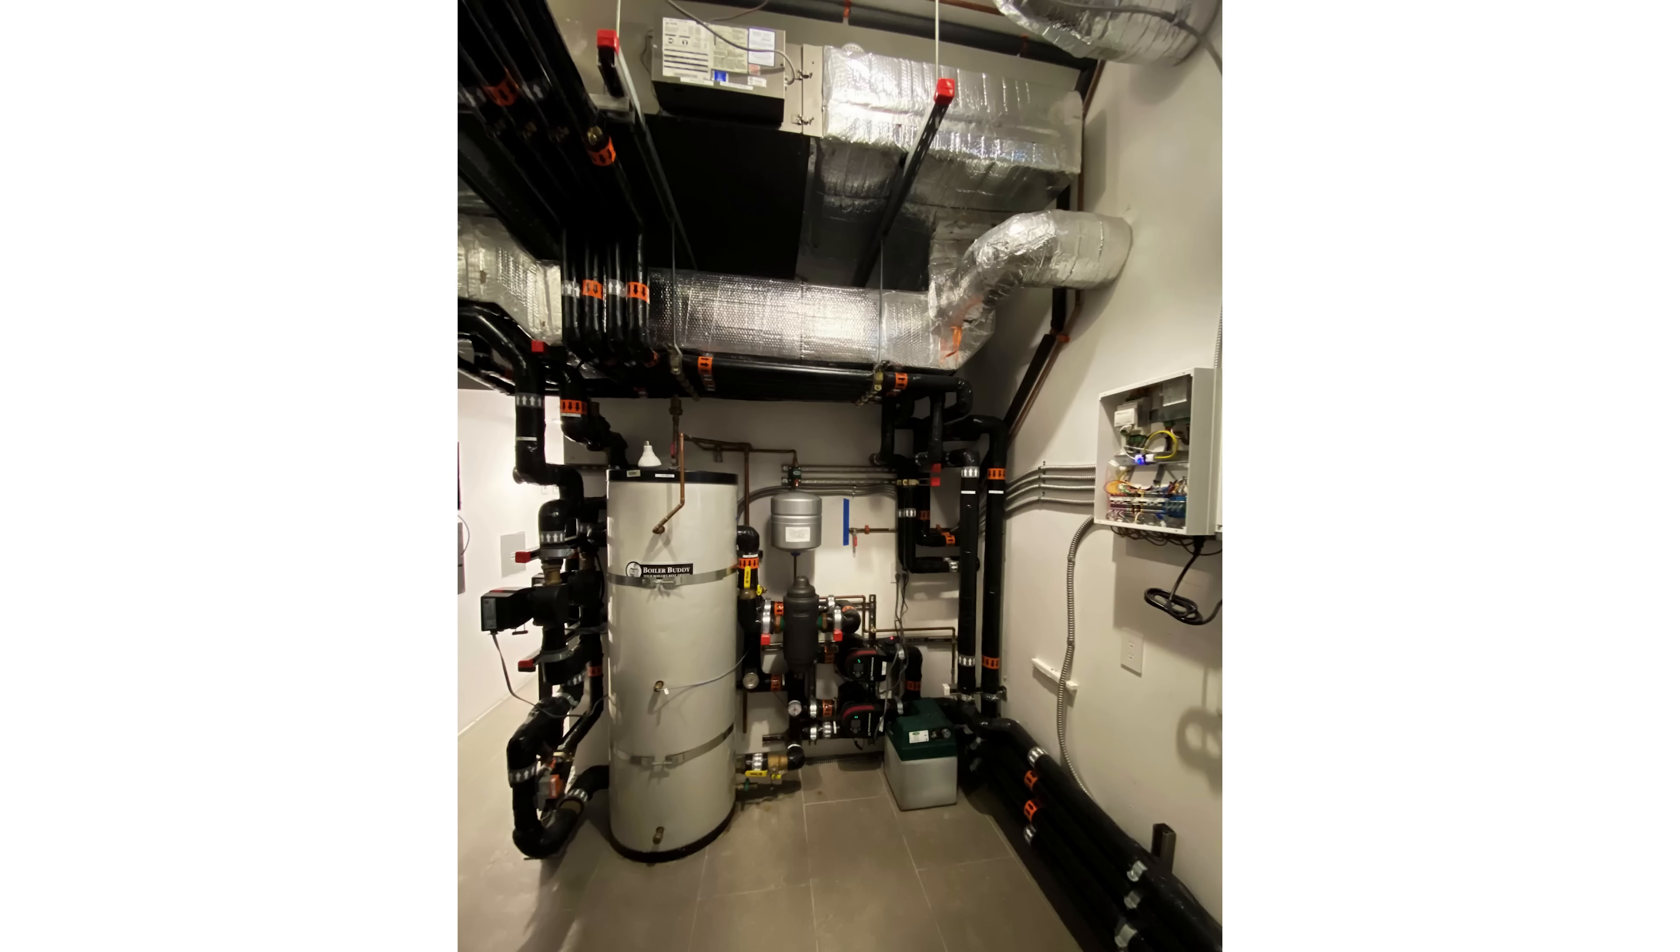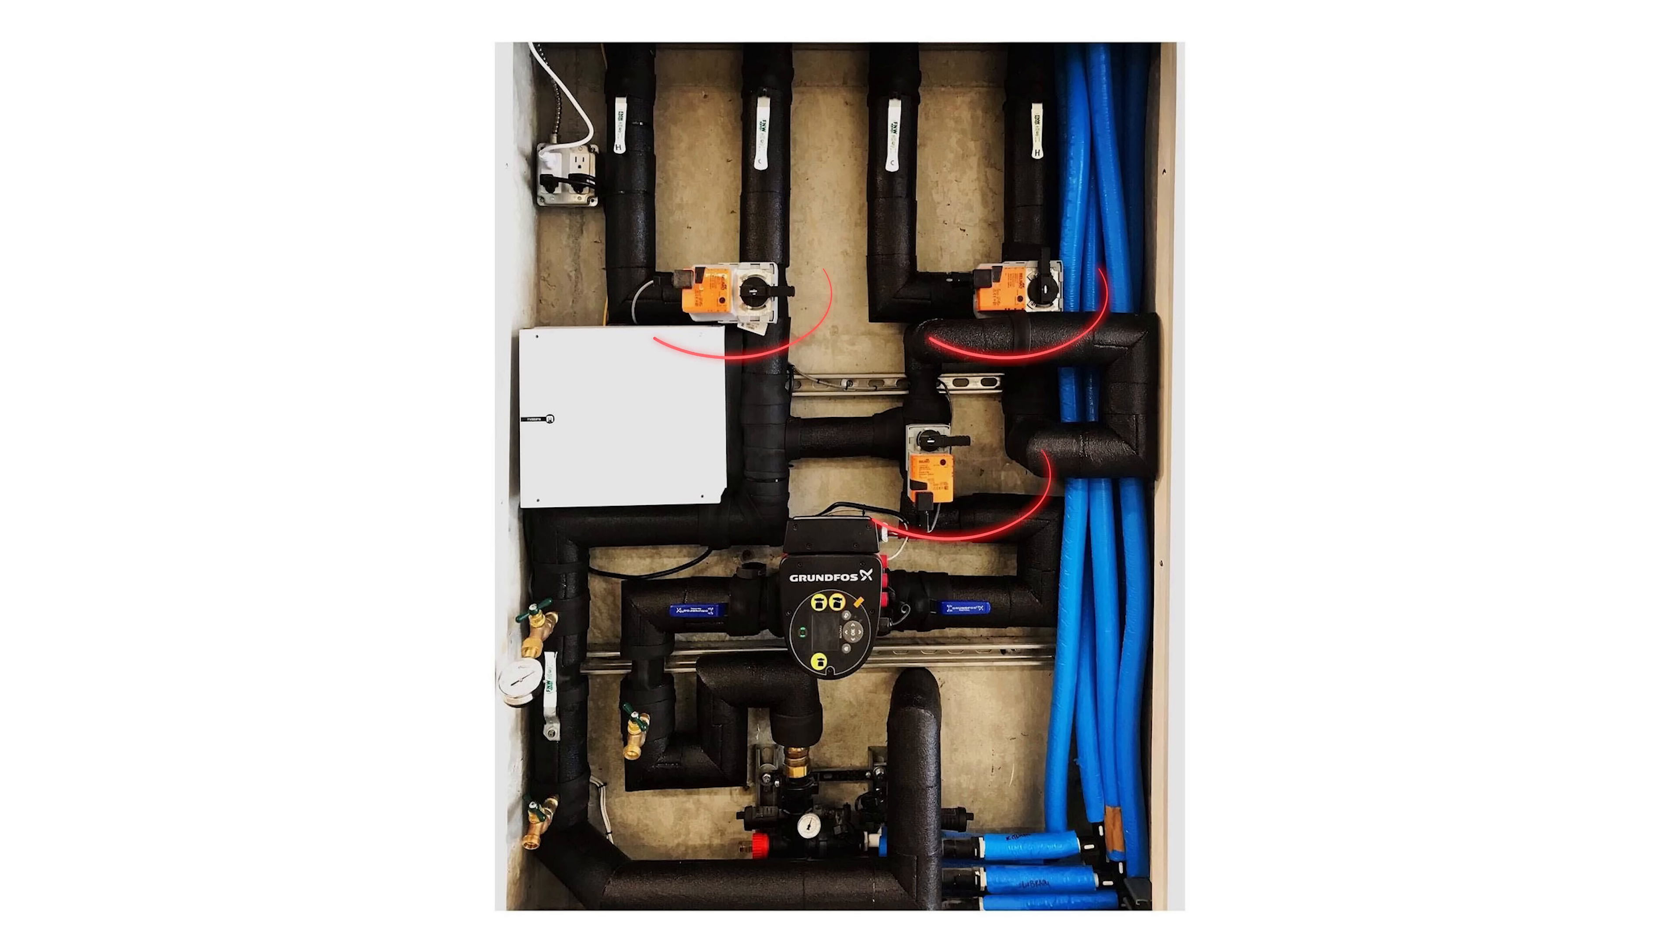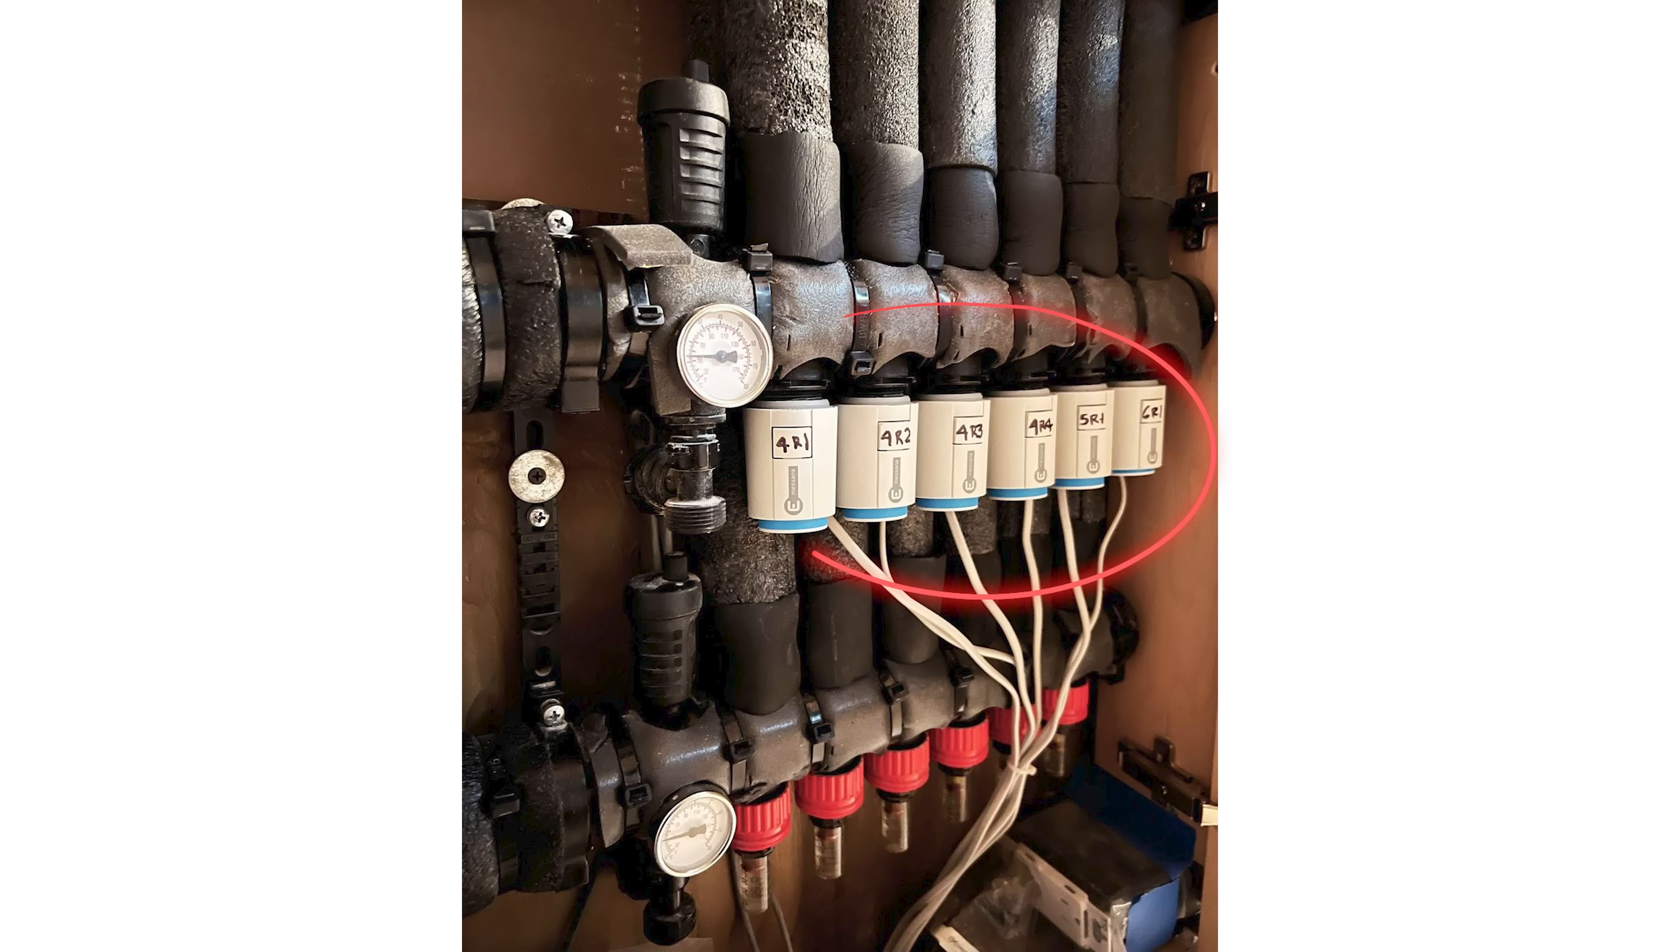But from there, where does it go? You'll be using pumps, buffer tanks, valves, and manifolds to push that water throughout your home to provide heating or cooling. And so typically there's a mechanical room in these projects. It's a dedicated mechanical space. And so you'll have all these pumps that push the water throughout the system. Then you have valves, which can adjust the radiant surface temperature or the supply water temperature to the system. It doesn't have to be radiant, but valves can make adjustments there. Then you'll have manifolds as well. And manifolds are what control the zoning of a home. And so typically we'll have each zone on its own manifold loop, and you can open or close these actuators on the manifold to open or close the loop for a particular zone. So you could choose when and where you're delivering heating or cooling.